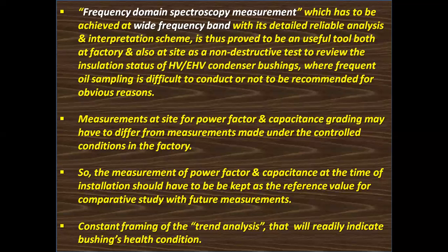So the measurement of power factor and capacitance at the time of installation should have to be kept as the reference value for comparative study with future measurements. Constant framing of the trend analysis will readily indicate the bushing's health condition.